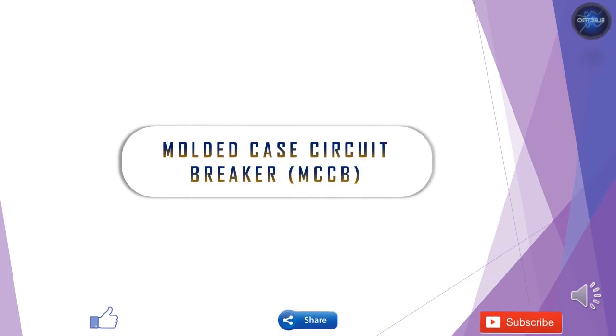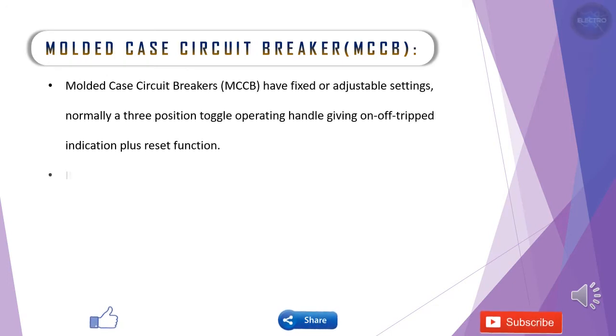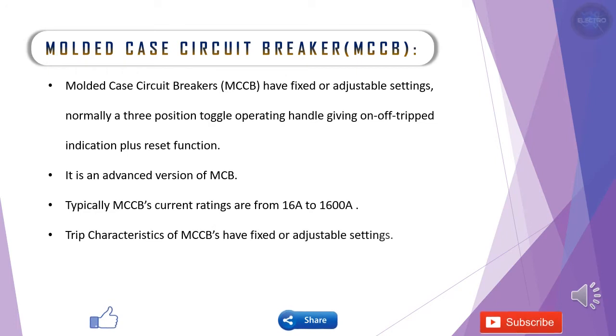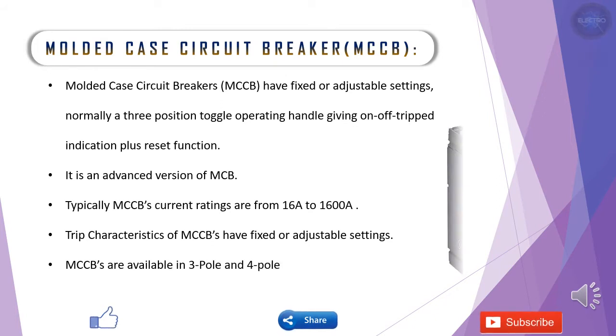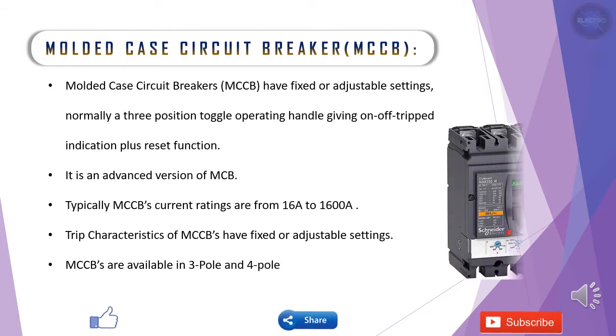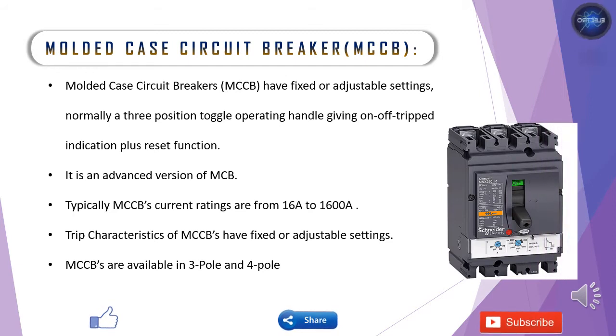Now we'll move to molded case circuit breakers — MCCBs. They normally have a three-position toggle operating handle giving on, off, and trip indication plus reset functions. This adjustable protection can be considered an advantage of the MCCB — you can tailor your output. The current ratings of MCCBs range from 16 amps to 1600 amps.